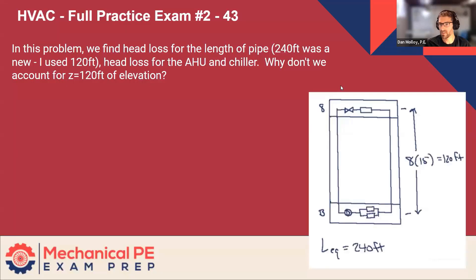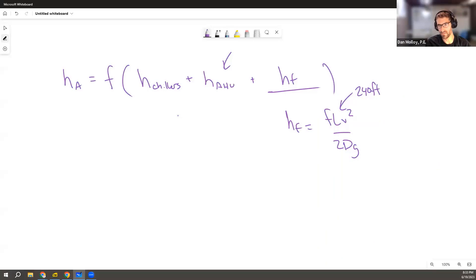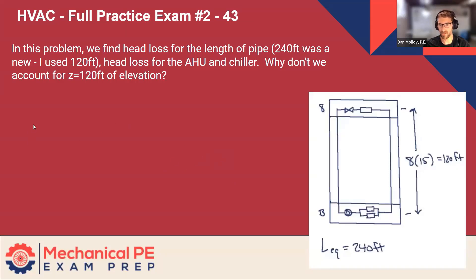It's actually probably a bit more than 240 feet, but the way I wrote this problem I was trying to make it a real-life example — a core riser, where the pipe goes straight up the building from the chiller and then straight back down. Not a lot of horizontal runs, so you should be within a reasonable level of accuracy. So good question. I think this comes up often — we get very used to accounting for the height when there's an elevation change. Why isn't that included? It's really important to know that for a closed loop, the pressure associated with that column of water being on both sides of the pump has a canceling effect. And this is all we need to get the answer. Good question — every candidate has to go through this kind of question at some point. Once you get it, you get it.